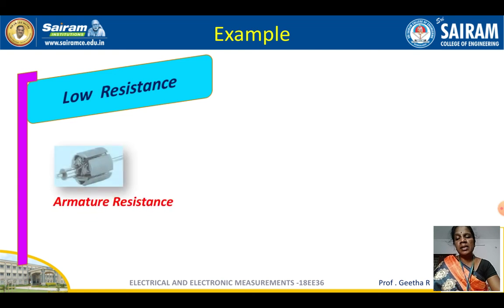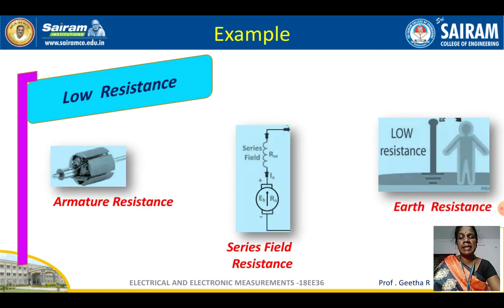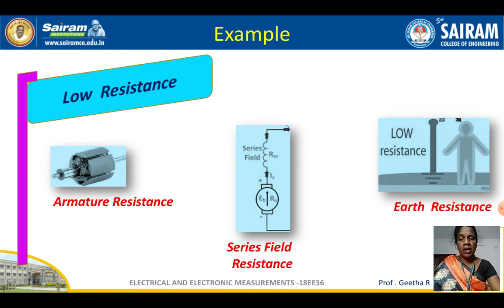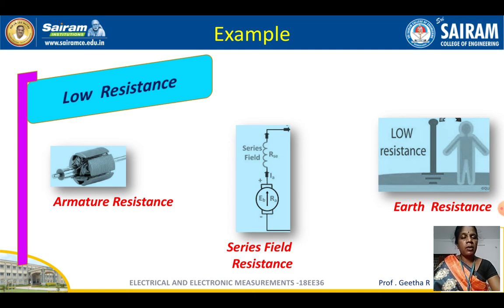Under low resistance, examples include armature winding resistance — that is below 1 ohm. Series field winding resistance also comes under low resistance. Earth resistance, electrode resistance, and earth rod resistance are all below 1 ohm and fall under the low resistance category.